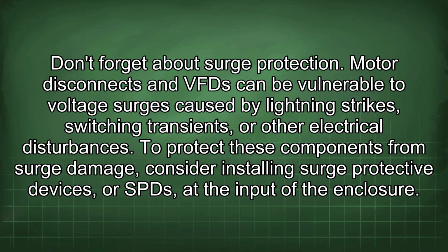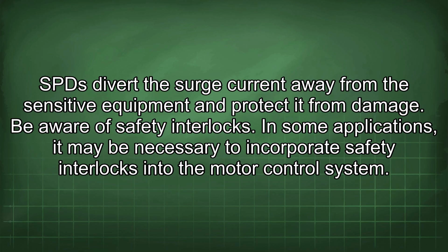Don't forget about surge protection. Motor disconnects and VFDs can be vulnerable to voltage surges caused by lightning strikes, switching transients, or other electrical disturbances. To protect these components from surge damage, consider installing surge protective devices, or SPDs, at the input of the enclosure. SPDs divert the surge current away from the sensitive equipment and protect it from damage.